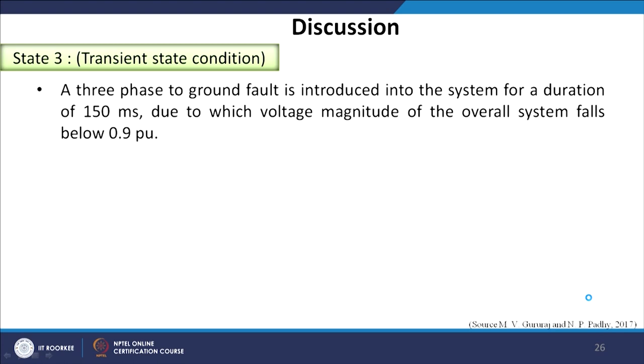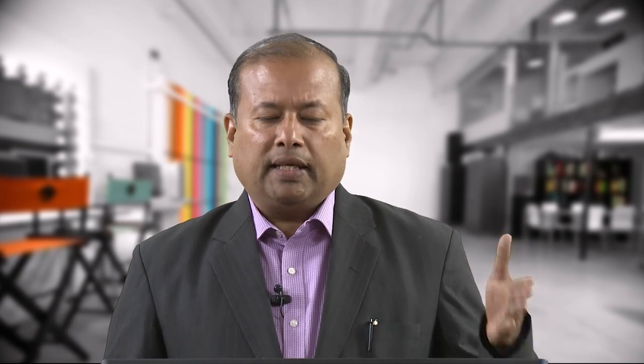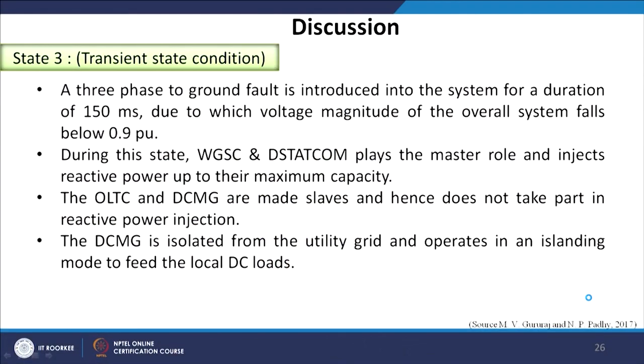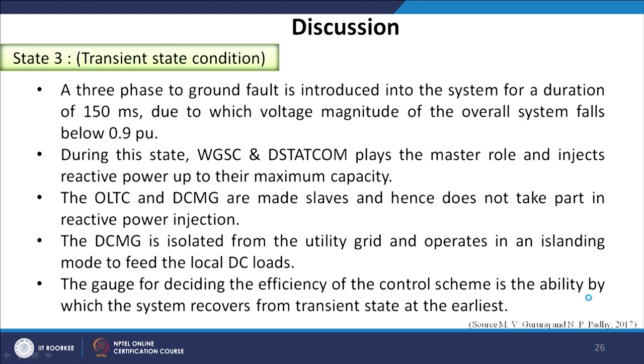Moving to the transient state: a three-phase to ground fault is introduced into the system for a duration of 150 milliseconds, causing the voltage magnitude of the overall system to fall below 0.9 per unit. During this state, both WGSC and DSTATCOM play the master role and inject reactive power up to their maximum capacity. The OLTC and DC microgrid are made slaves and do not take part in reactive power injection under transient state conditions. The DC microgrid is isolated from the utility grid and operates in islanding mode, feeding the local DC loads.